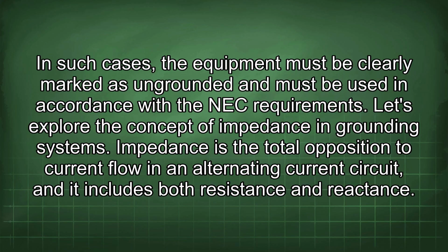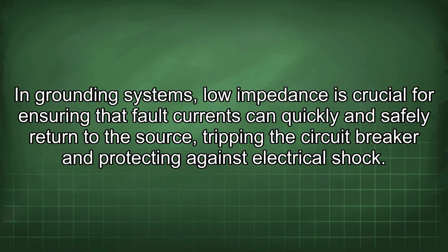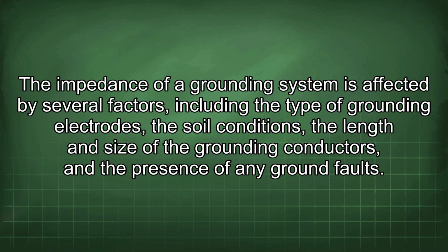Impedance is the total opposition to current flow in an alternating current circuit, and it includes both resistance and reactance. In grounding systems, low impedance is crucial for ensuring that fault currents can quickly and safely return to the source, tripping the circuit breaker and protecting against electrical shock. The impedance of a grounding system is affected by several factors, including the type of grounding electrodes, the soil conditions, the length and size of the grounding conductors, and the presence of any ground faults.